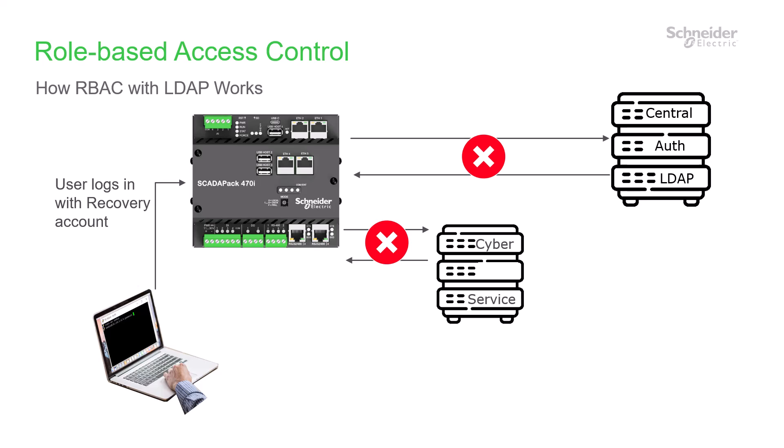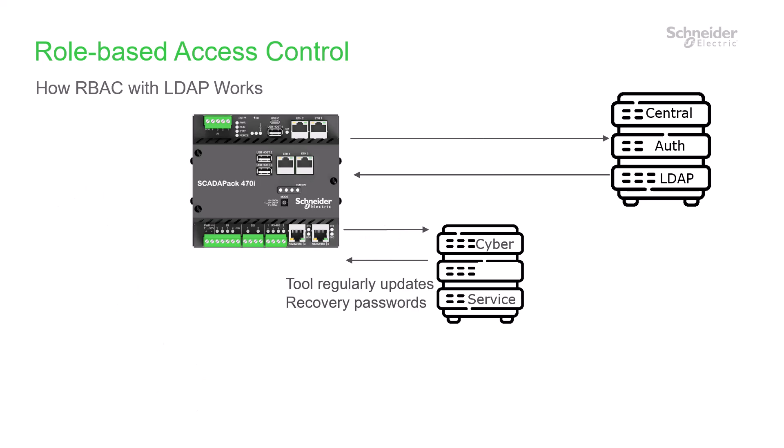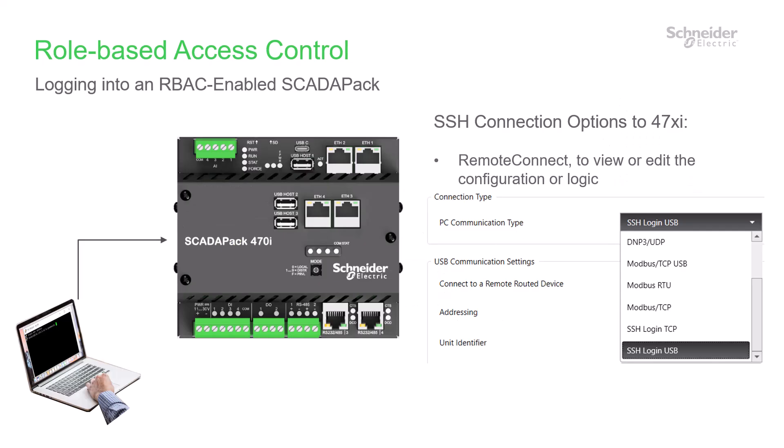You can then log in using the recovery account credentials, and after communication is restored, the recovery credentials will again be updated. You can log in to an RBAC-enabled SCADAPack using Remote Connect to view or edit the configuration or logic. In the PC communication settings, a connection type of either USB SSH or TCP SSH may be selected.